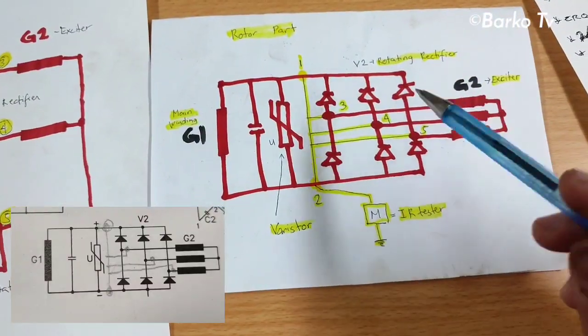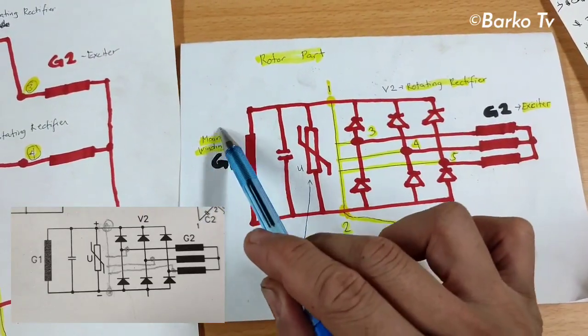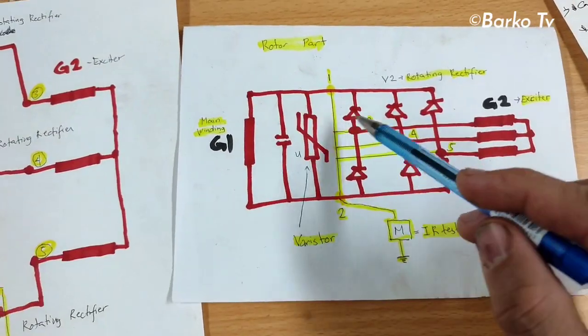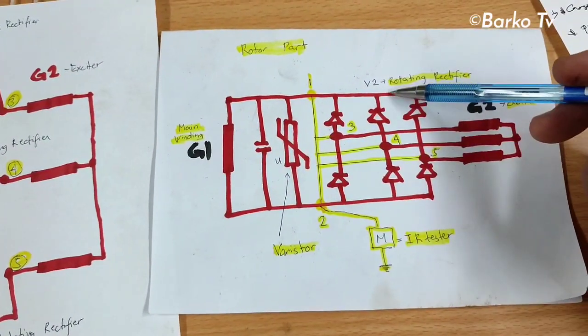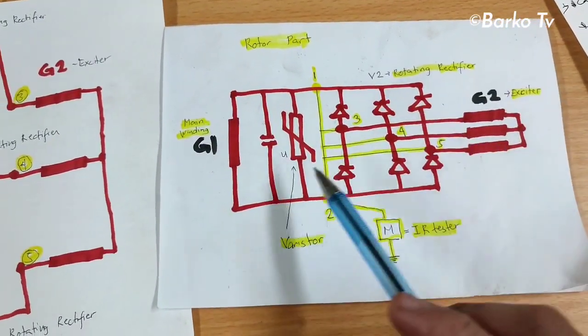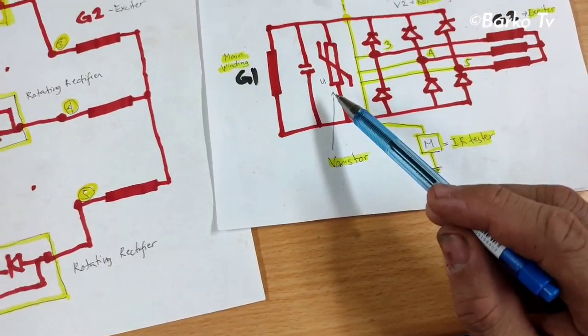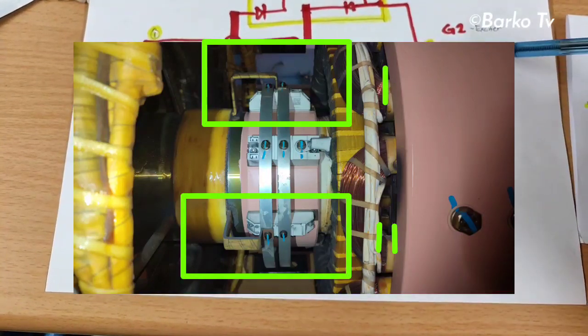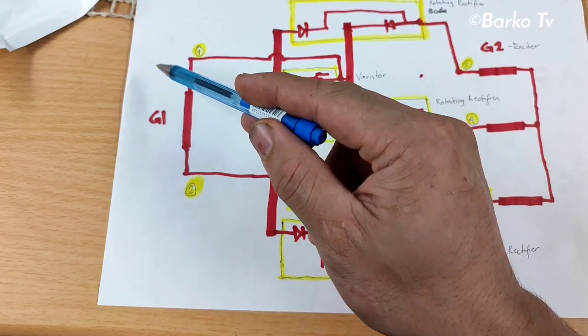We need to check the diagram so we understand properly. This is the rotor part. Labeled main winding G1 — that is the stator main winding — connected with varistor. That is the rotating rectifier: one, two, three — three sets of rotating rectifier. G2 is the exciter. In the schematic there is only one varistor, but in actual there are two pieces.